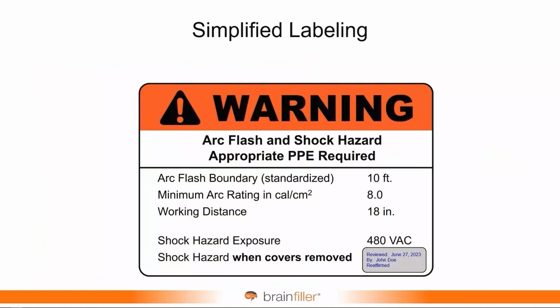I have an alternative labeling method that I developed years ago. I have had an article published on this, a video, and the industry has actually been embracing this method. And here's what it is. For the arc flash boundary, standardize on a boundary, 10 feet, for example, for low voltage. Put the word standardize there because the true boundary is 1.2 calories a square centimeter. Someone may say, hey, it's 10 feet where you actually have 1.2. Well, no. So put standard there, and then just list the arc rating of the PPE, because that's all you really need. The end user, they don't care if you have 5.2, 2.6, 3.8 calories a square centimeter. For the person performing the work, they just want to know what to wear. So 8-calorie PPE, keep unprotected people back 10 feet.